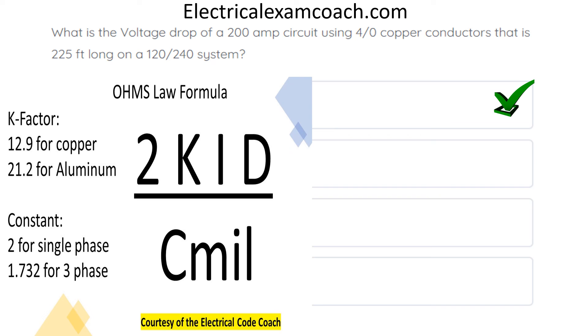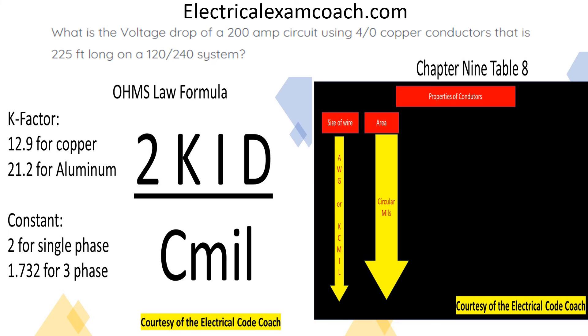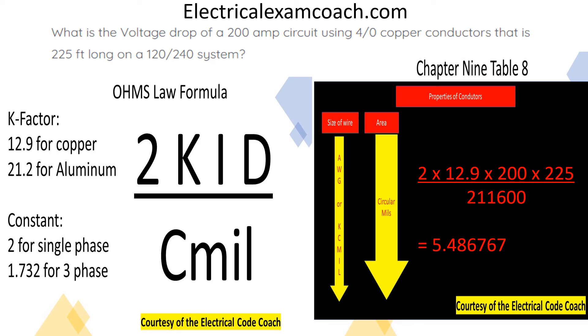For this one, we use our Ohm's Law formula: 2KID divided by Cmils. We have 2 as our constant, K-factor is 12.9 because it's copper, then our current and distance divided by Cmils. We head to Chapter 9, Table 8, start on the left-hand side to find our 4-aught conductor, then cross over to get our Cmils. Plugging in: 2 multiplied by 12.9 multiplied by 200 multiplied by 225, divided by the circular mils of a 4-aught copper conductor equals 5.487. We round up to 5.5 volts.